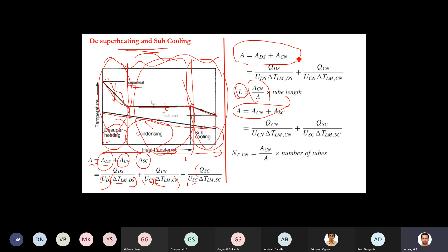So total A is known. So ACN by A times the total tube length will give the length required for the condensation zone. Similarly, you can calculate the length required for the remaining portion, de-superheating. Otherwise, you can calculate the number of tubes also. So NTCN, the number of tubes for condensation, is ACN by A, times the total number of tubes.